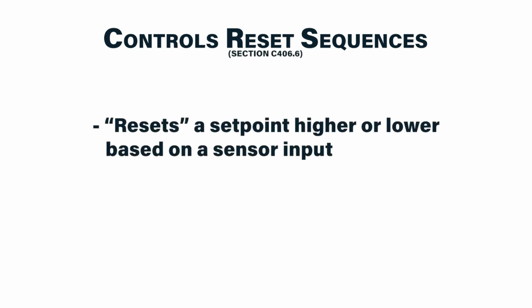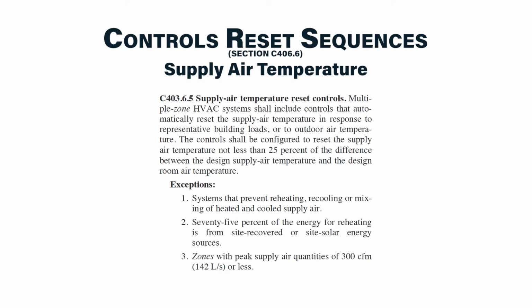The last updates I want to touch on are requirements for reset sequences for multi-zone air systems. A reset sequence is a sequence that will reset a set point, higher or lower, based on another sensor input, such as outside air temperature. One example of a reset sequence is the supply air temperature reset sequence, which was required in the 2009 code. The traditional reset sequence typically resets the supply air temperature set point based on the outside air temperature. How much you reset is up to the designer or the operator, but the 2018 code requires that this must be at least 25% of the difference between the supply air temperature and the design room temperature.